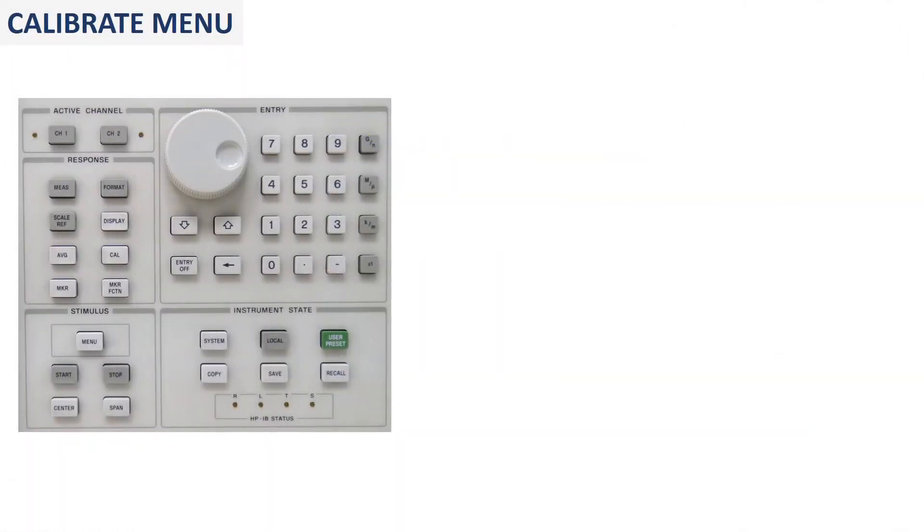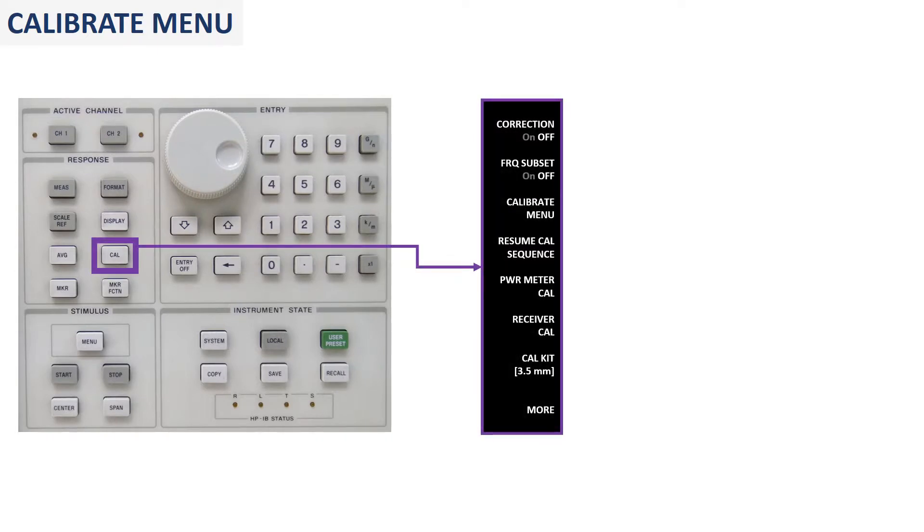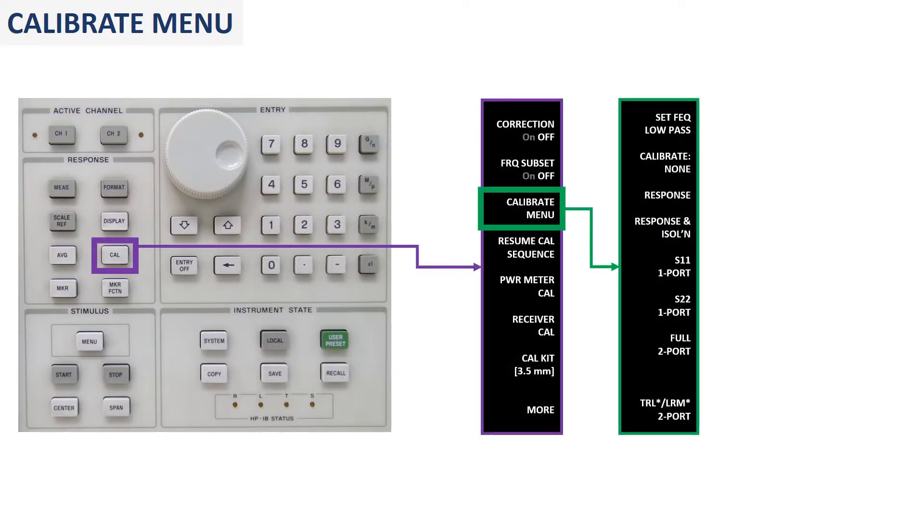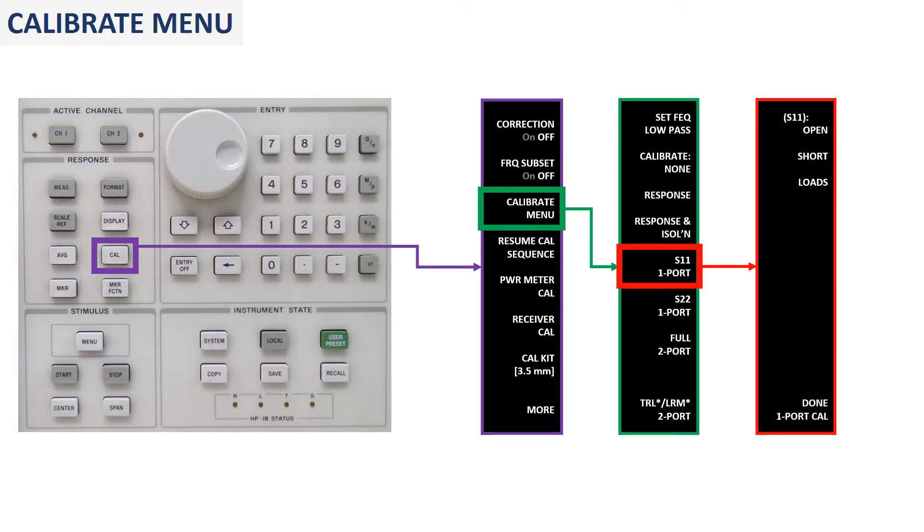Next step. I press the Calibration key and then the soft key Calibrate Menu. Then we specify S1,1, one port, and the one port calibration menu is on.